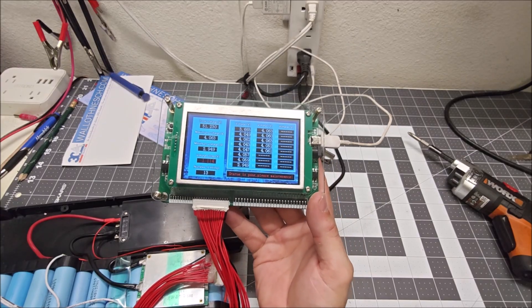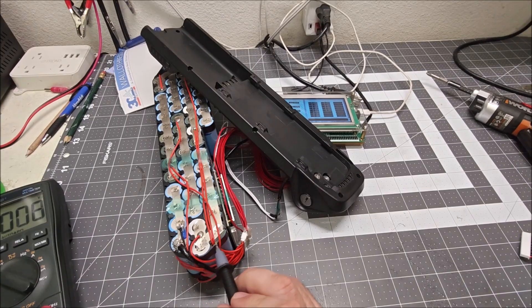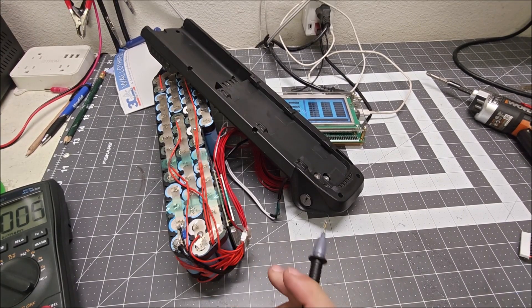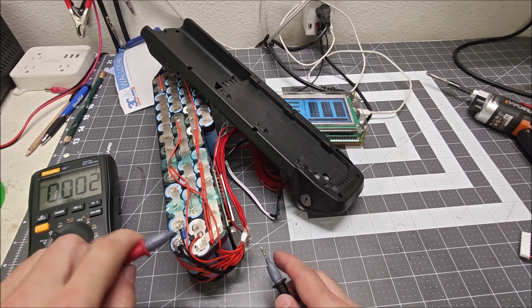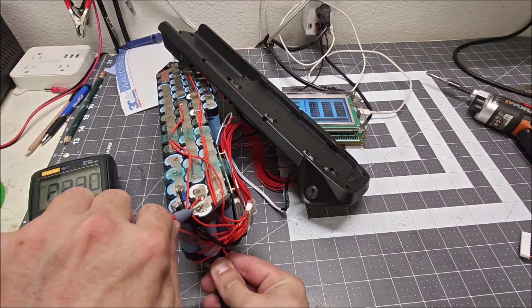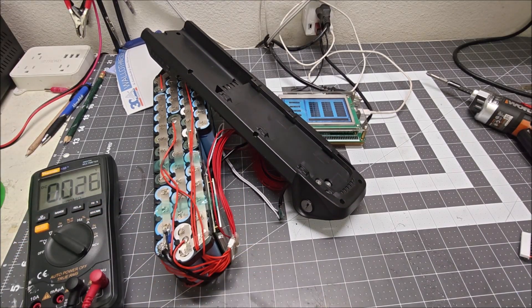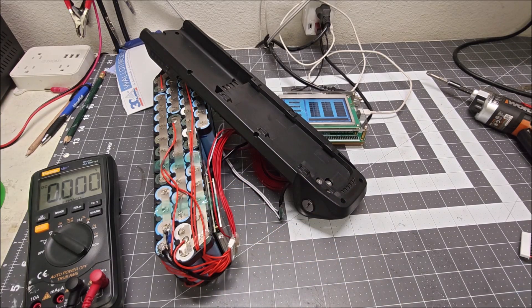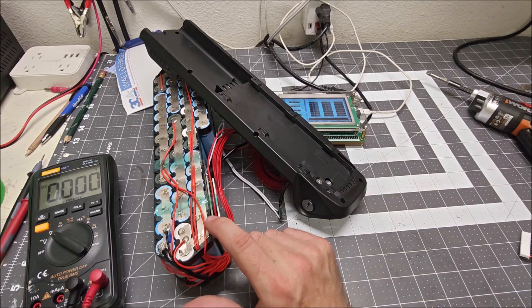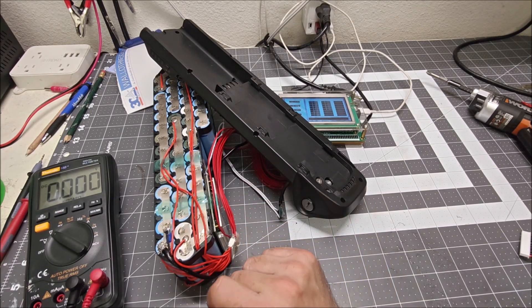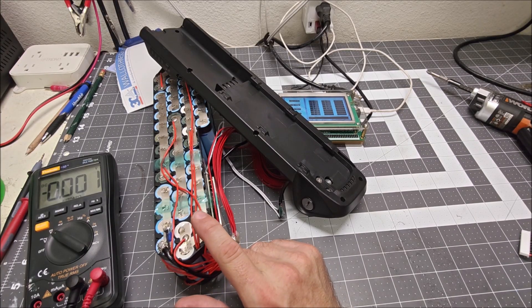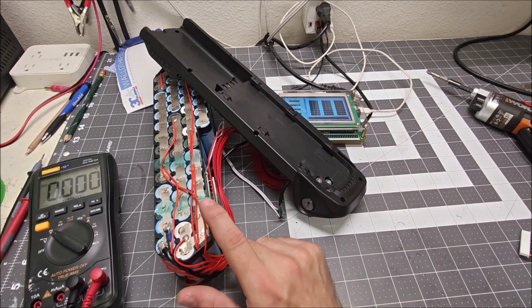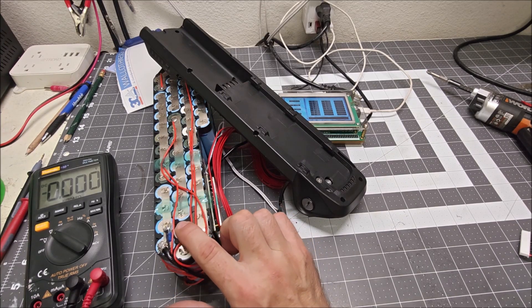It is this set of four here: one, two, three, and four. These are the ones producing 2.9 volts. Let me get the battery on here. Yeah, this is your 2.9, so these four are our suspect batteries here. Now I can pull out these batteries. I can clip the plastic leads and remove the battery, but then I got to figure out which is the bad cell.